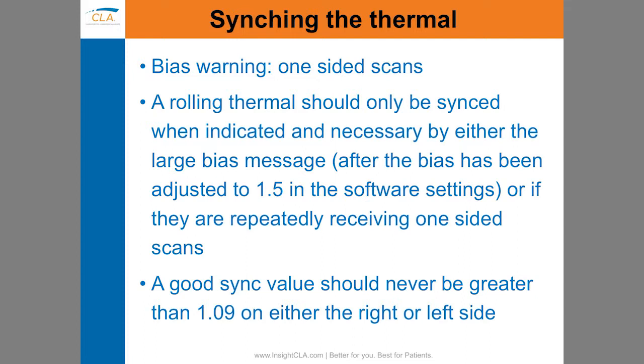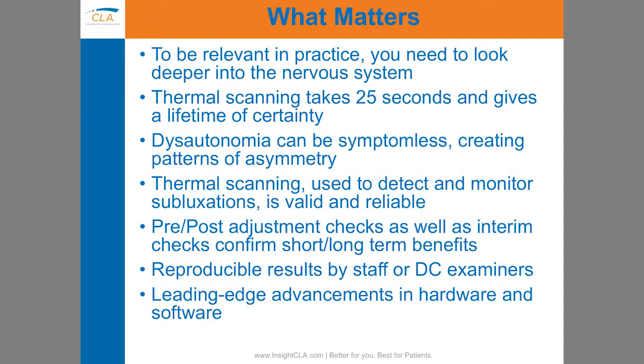Syncing is in the user guide, the ability to do it, and it's an exceedingly simple set up system so you can sync the thermal on the fly when the patient is in there if you need to, and do it ahead of time. If you are getting signals or flags, make sure you do it before you're starting the next examination.